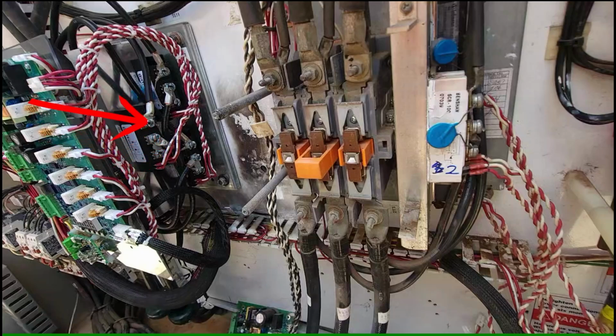We're trying to use this as a gradual pass-through where we can cycle this SCR gate rapidly and gently apply power to the motor. So you'll see that there's a bus bar that connects the positive and negative. So that's what these 2 and 3 are. They're a positive and negative bus. And by putting a bus bar between there and then connecting our motor leads to the other side, here, here, and here, we can maintain our AC output. This confuses some when they're used to the drive perspective. So by combining the 2 outputs, we maintain our AC output through the SCR, but we can control how much output comes out of it.